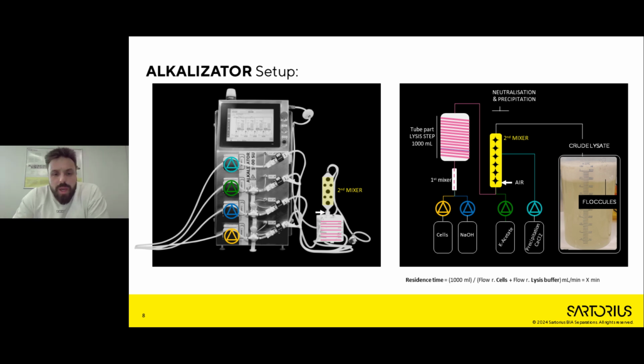All right, and this is how it's then continuously pumping the solutions. The pressure sensors monitor that you don't reach over 1.5 bar. Usually the working range is somewhere between 0.3 and 1 bar, so you are well below the 1.5 bar limit.